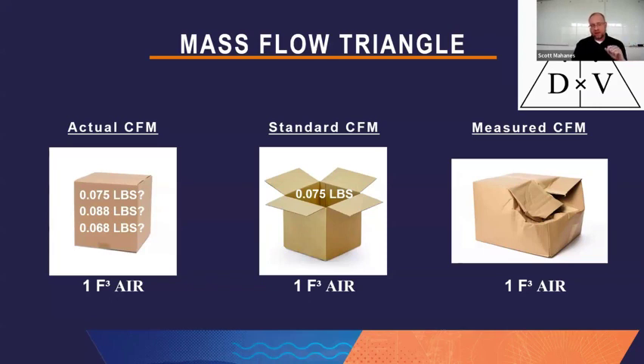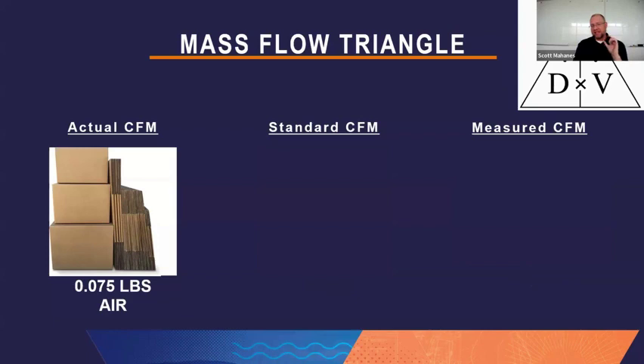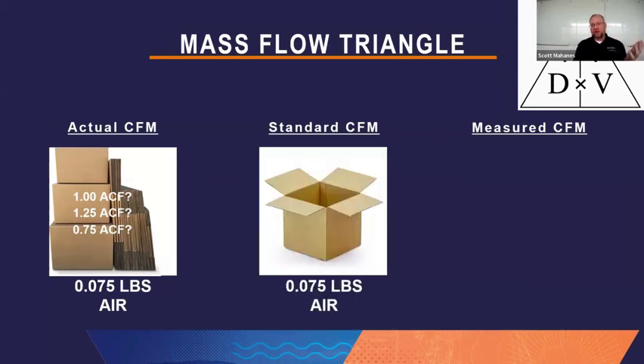But this is what it kind of ends up being. And you have a question about whether the volume is correct or even the mass. You can reverse this and say, well, what if I ordered 0.075 pounds of air, the mass of air, from Amazon? When it comes to my doorstep, it's going to come in different size packages. There's no guarantee of the volume that it's going to come in. So it could be standard at 1 cubic foot. It could be a little bit larger. It could be smaller. And then with standard CFM, the difference is there's no surprise. I know it's always going to be the same size box every time.